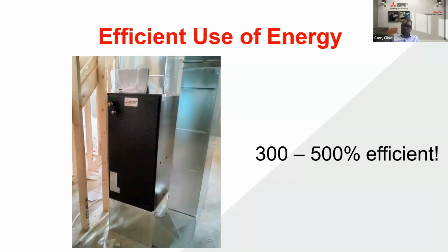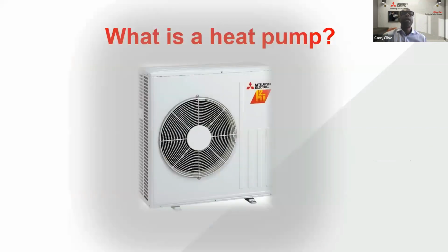And this is what you see in our cold climate heat pumps, in that it's capable of holding its rated heating capacity. So the amount of heating output of the system, it can hold that high capacity heat down to temperatures as low as -15. Once you get to -15, it starts to taper off in the amount of heating output that you achieve. So I'll explain further as I go throughout the presentation, and we talk more about sizing the heat pump to meet your load. But the fact remains that the air source heat pump is one of the most energy efficient products that you could use to heat your space.